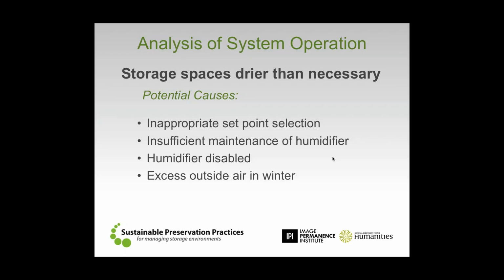as they get older. Oftentimes, humidifiers are also a seasonal operation, so we see a lot of instances from institutions where it's seasonally turned on and off. In the spring, someone will go in and valve the humidifier closed, and in the fall, it's their job to go back in and open up that valve so that water or steam can get to the humidifier and work within the system. If someone forgets to open that valve, or that yearly preventive maintenance check is missed, then all of a sudden you can go for months at a time without getting any humidification. The other one is making sure that you don't bring in too much outside air.